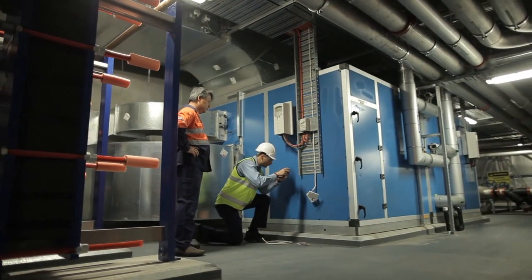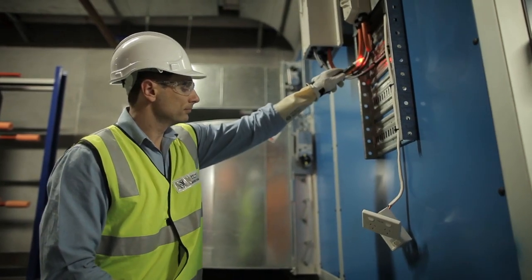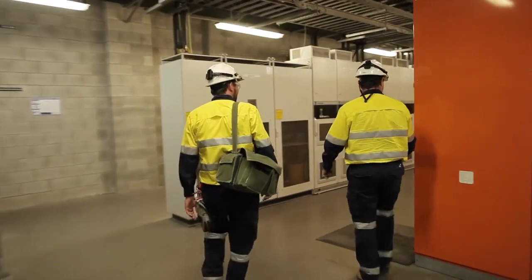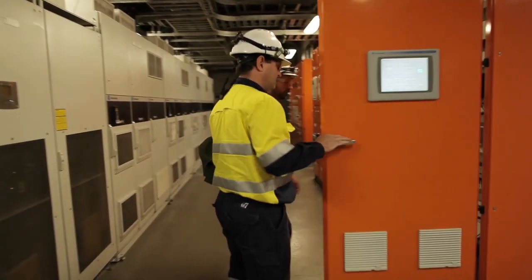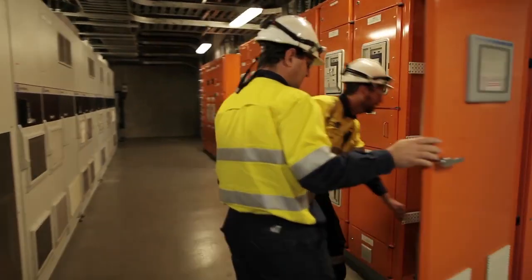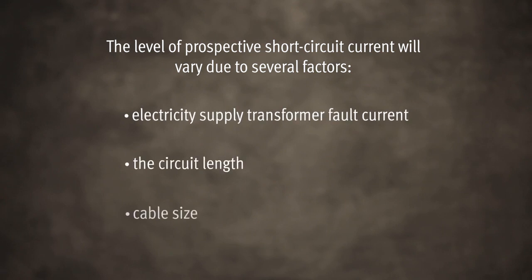High fault currents are not just limited to large main switchboards. They can also occur within other locations of the installation, such as smaller switchboards, electrical supply pillars, or large electrical equipment. The level of prospective short circuit current will vary due to several factors, such as the electricity supply transformer fault current, the circuit length, and the cable size.